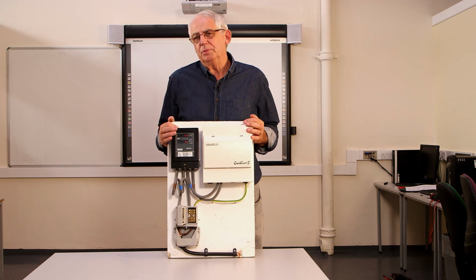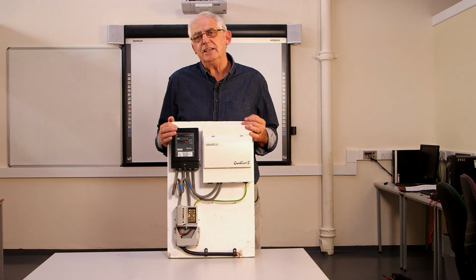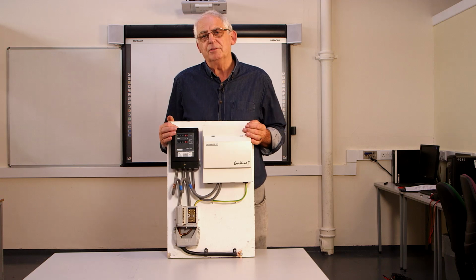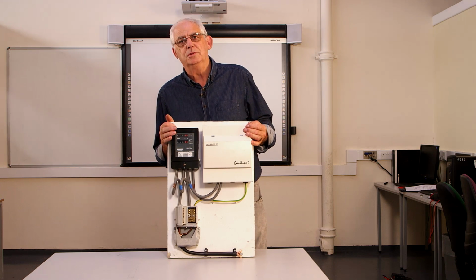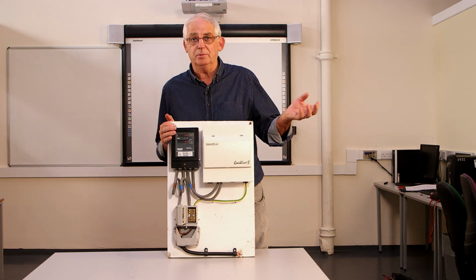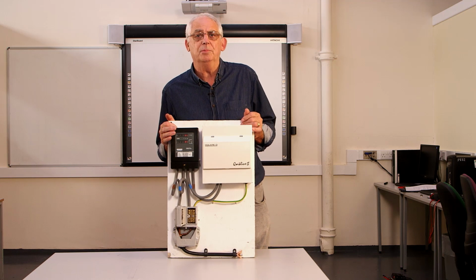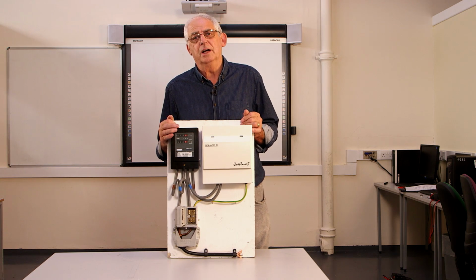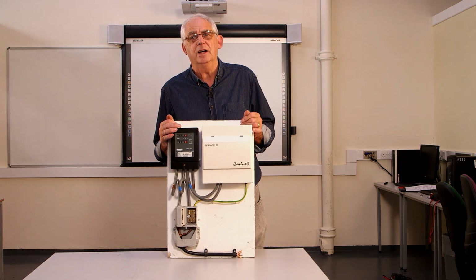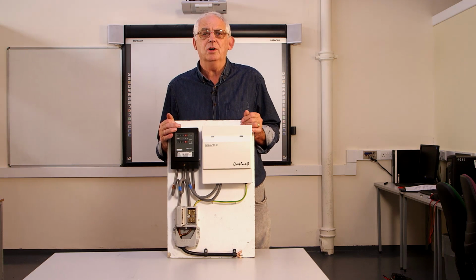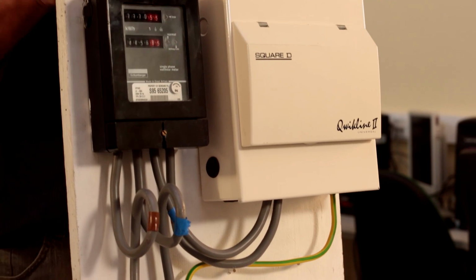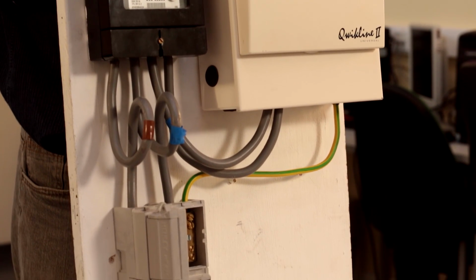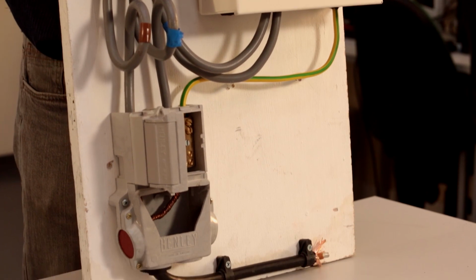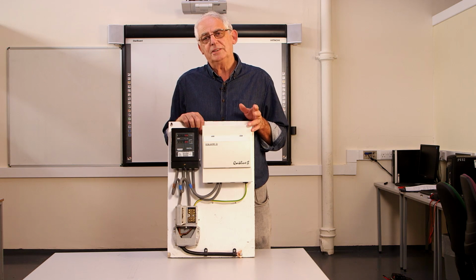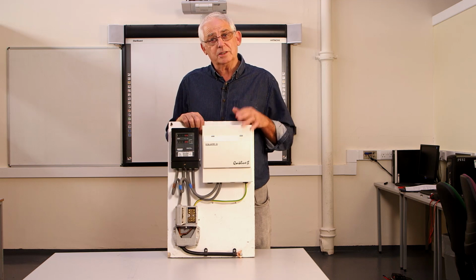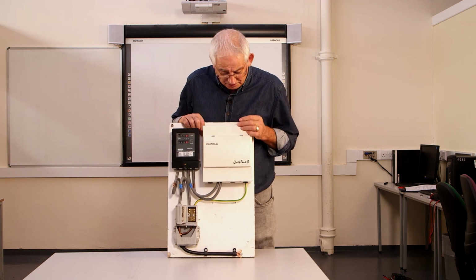Right, the next earthing arrangement we want to look at is a TNCS system. Slightly different because it uses the neutral, which is in the supply cable, as our earth fault return path as well. That neutral conductor is called a PEN conductor, which stands for protective earth and neutral. Now, the difference between this and a TNS system is that with a TNS system, we use the sheath of the supply cable. TNCS system, as the cable's only got two cores, and it's a concentric cable.